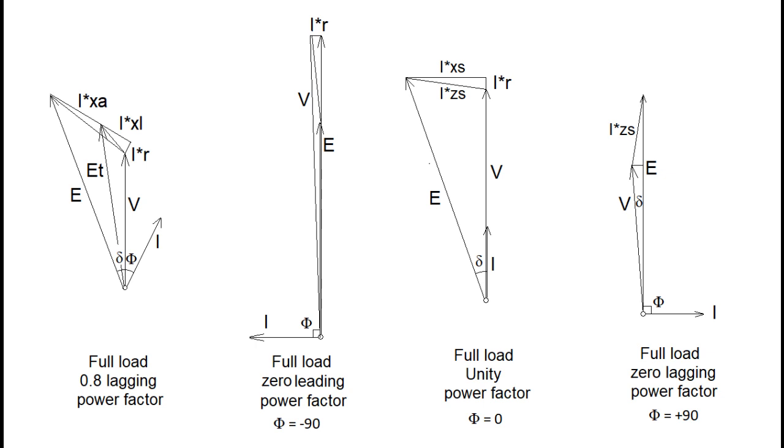In conclusion, we say that terminal voltage is a very variable parameter with changing load current and load power factor. Practical load requires constant terminal voltage. To seek constant terminal voltage, excitation must be continuously changed with load current and power factor.